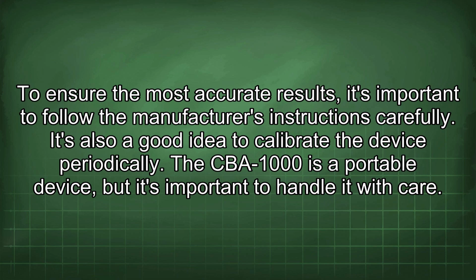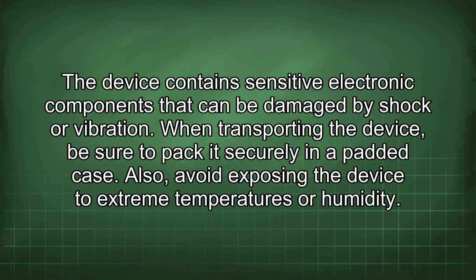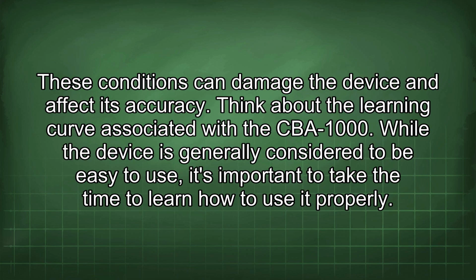The CBA-1000 is a portable device, but it's important to handle it with care. The device contains sensitive electronic components that can be damaged by shock or vibration. When transporting the device, be sure to pack it securely in a padded case. Also, avoid exposing the device to extreme temperatures or humidity. These conditions can damage the device and affect its accuracy.